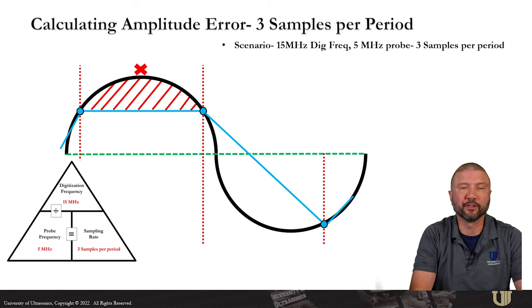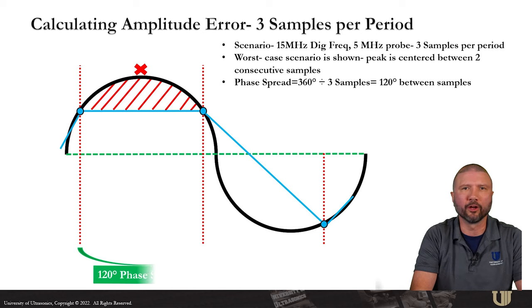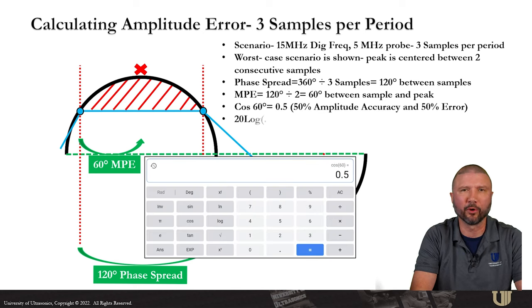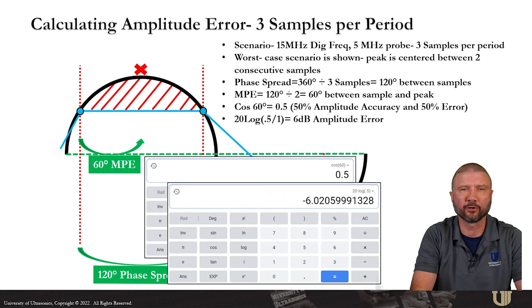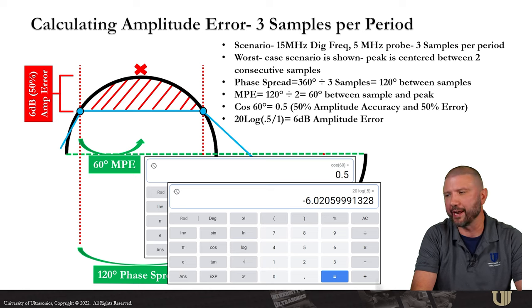So now let's consider a different scenario. I've got a 15 MHz digitizing frequency and a 5 MHz probe, which would give me three samples per period. A worst case scenario is shown where the peak is centered between two samples. Phase spread would be 120 degrees between samples. And if I divide that by two, I get my maximum phase error of 60 degrees. Cosine of 60 degrees is 0.5, which means 50% accuracy and 50% error. Convert that to a dB and I can show that I have 6 dBs of amplitude error at this condition.